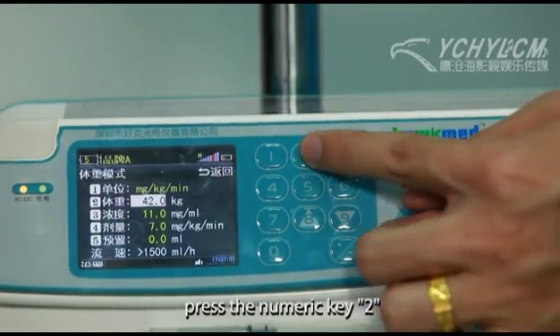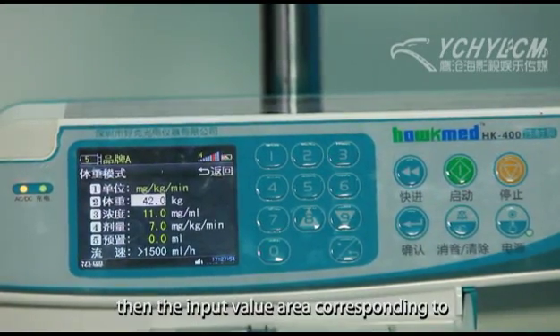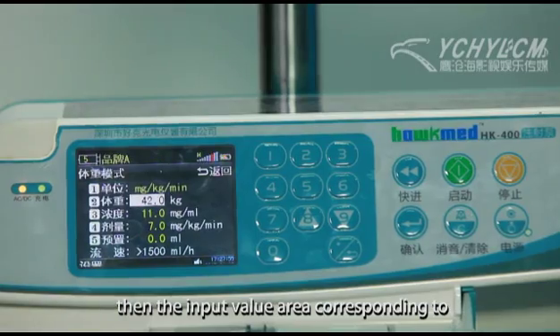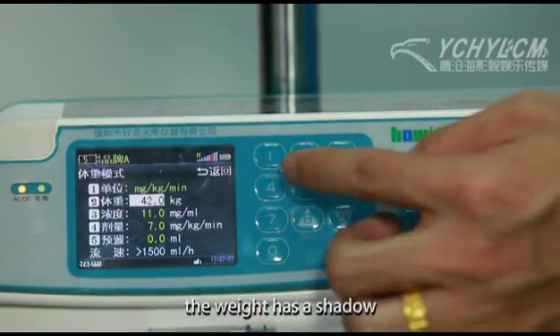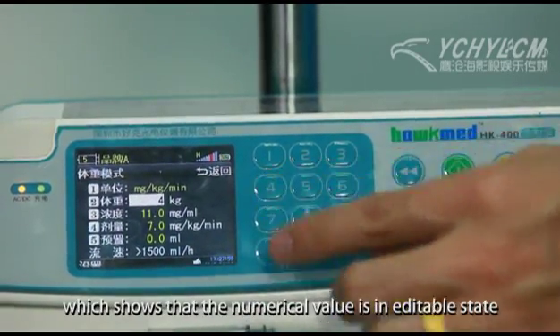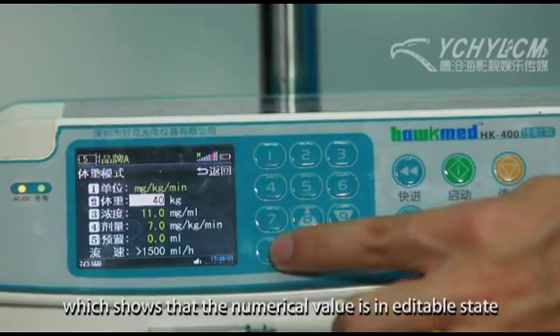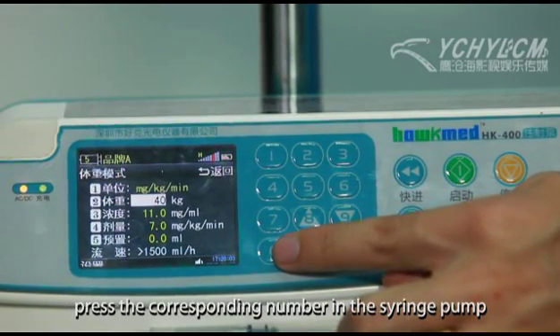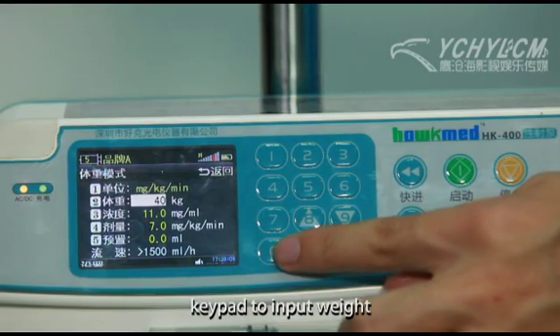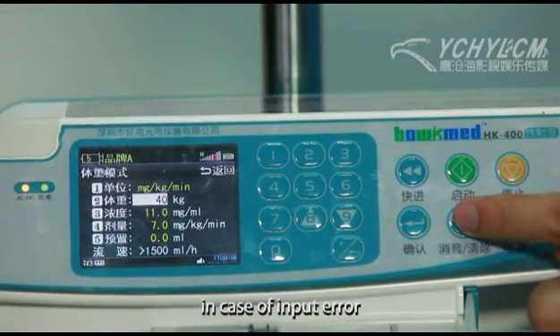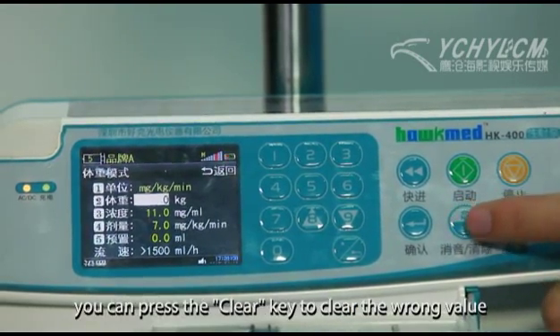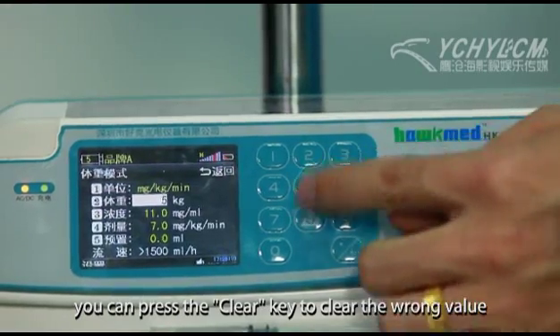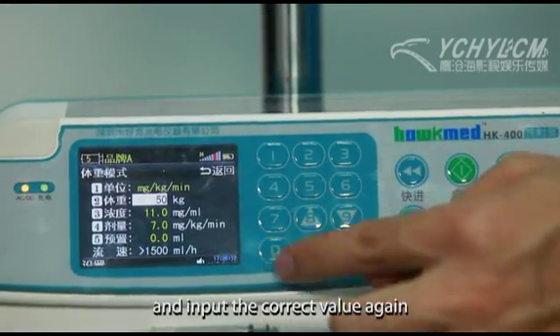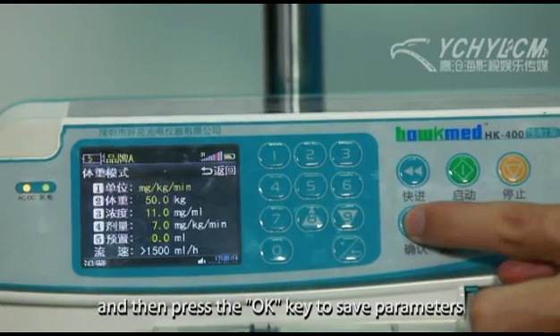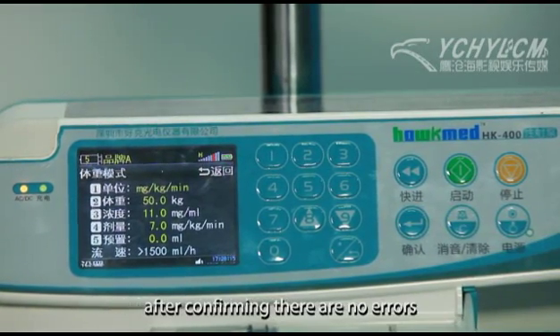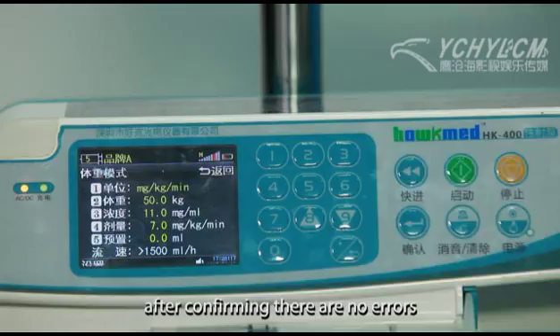Setting weight. Press the numeric key 2, then the input value area corresponding to the weight has a shadow, which shows that the numerical value is in editable state. Press the corresponding number in the syringe pump keypad to input weight. In case of input error, you can press the Clear key to clear the wrong value and input the correct value again, and then press the OK key to save parameters after confirming there are no errors.